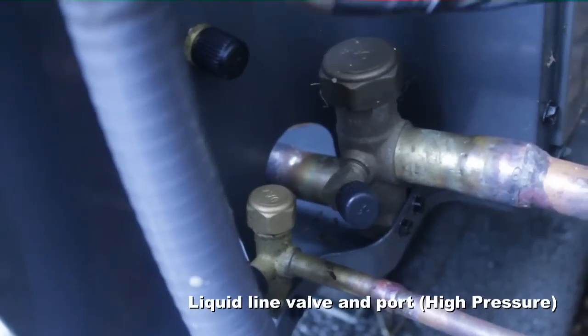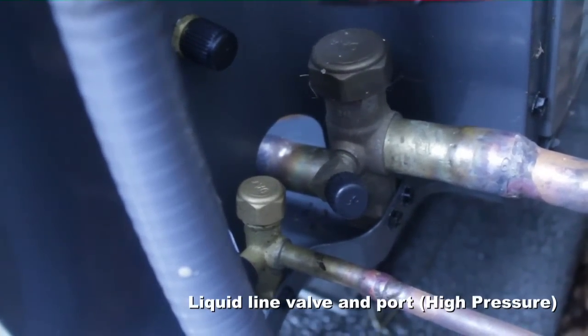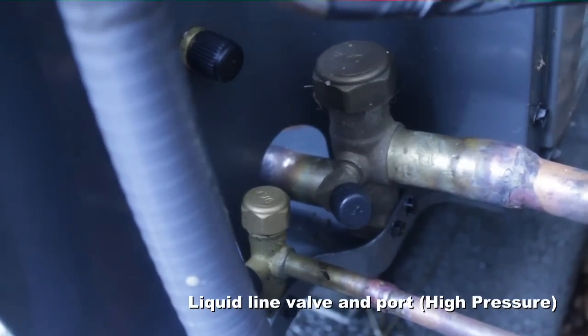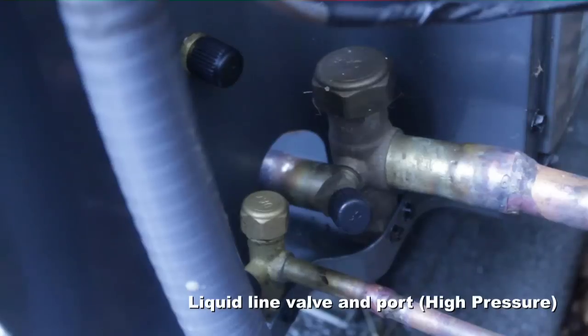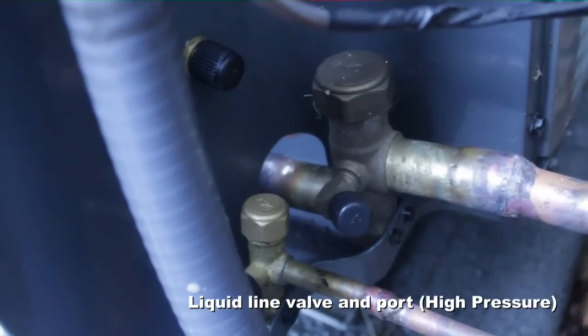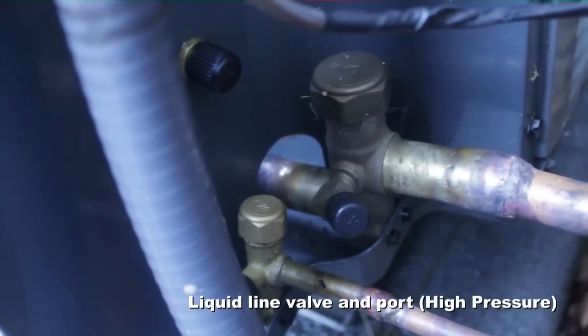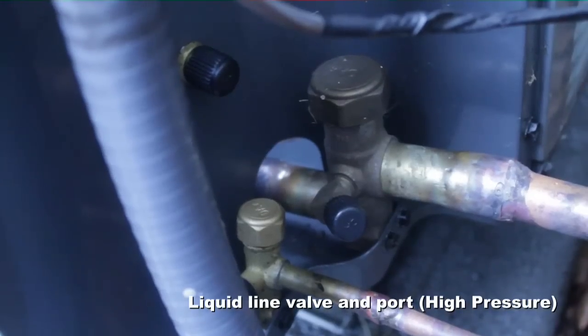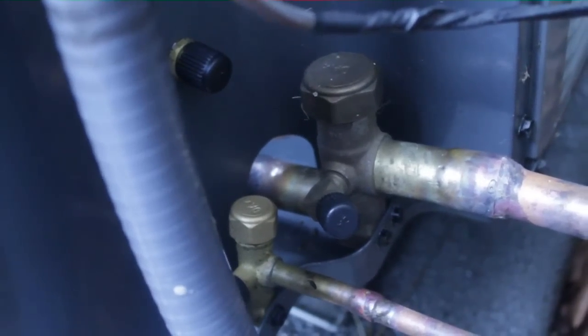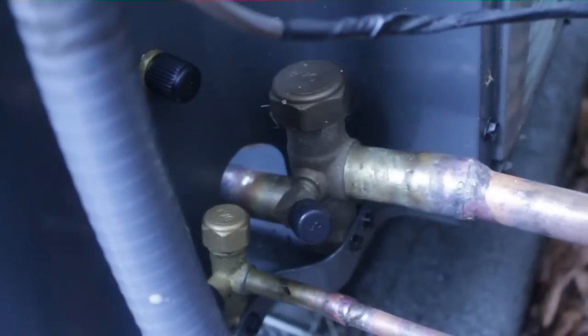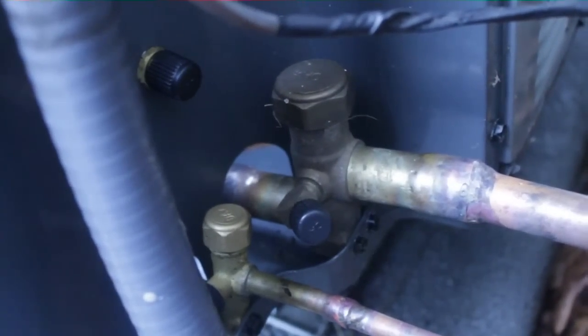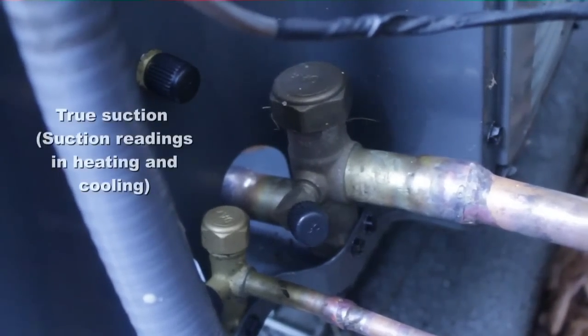In heating, it's flowing in the opposite direction. That is why we have bi-flow filter dryers. It is coming back from the condenser, which is now at the air handler or furnace in a dual fuel system. In both cycles, it is the liquid line.